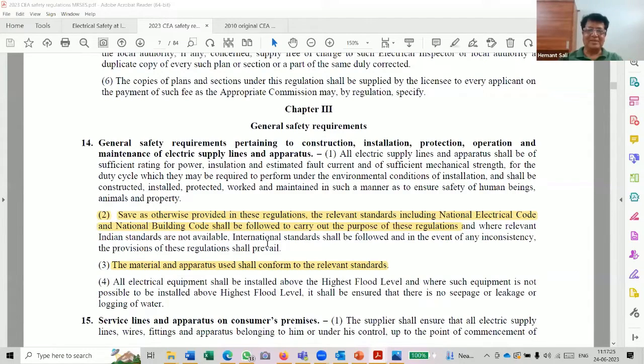Yeah, so this is actually the result of our persistent efforts for this change in a small word, because "shall be" and "may be" make a lot of difference. "May be" gives the person who refers to the regulation the option whether to use it or not. And "shall be" makes it mandatory. So whatever has been given in the regulations, it now says that the standards and codes are mandatory. See, when the bare law is there, it doesn't give you all the interpretations. On that bare law, a lot of books come out and they give the detailing. Like that, this is the bare regulation.